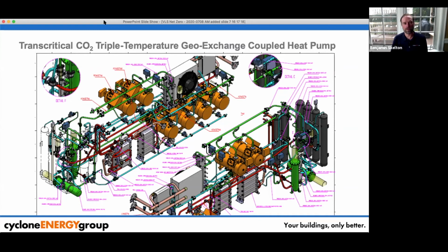Going back to the design: as Alan mentioned, in the northern climates most of our projects pursuing zero energy strategies use ground source geo-exchange heat pumps. A lot of people call them geothermal heat pumps, but I prefer the correct name, geo-exchange. We do that because the ground up here in northern climates, below about 4 feet, stays around 55 degrees constantly. That gives us a stable source for energy exchange, as opposed to air source, where we fluctuate from -10 to 95 degrees, over 100 degrees of temperature swing in a season, and air source systems have different efficiencies across that whole range, so it can be a challenge to make it work.